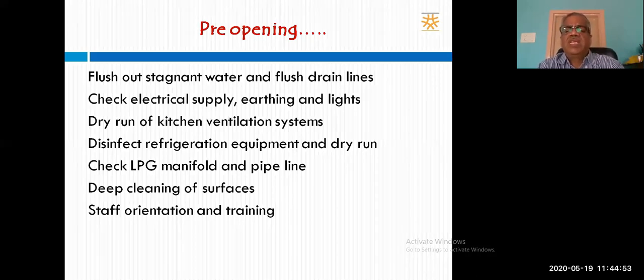Then disinfect all the refrigeration equipment, because once sealed in an airtight compartment, we don't know what might have grown there - some unwanted microorganism or fungus. So reopen the entire refrigeration equipment, wash them, disinfect them, sanitize them, keep them open for a day, then close and do a dry run for at least 24 hours - not less than 24 hours in any case.